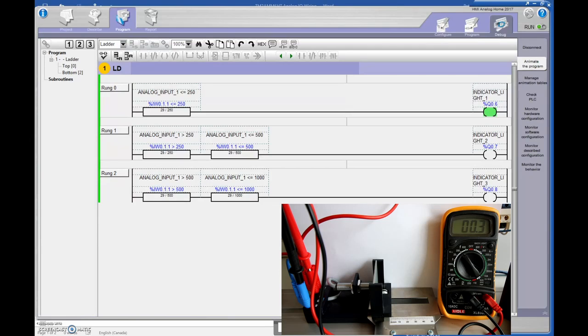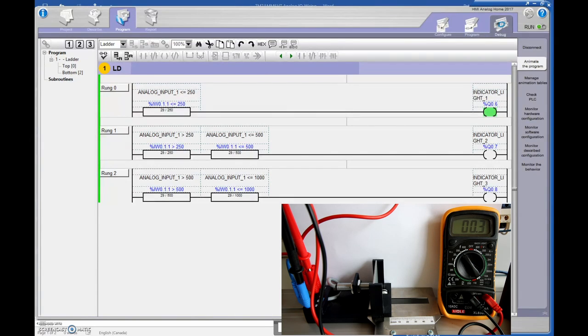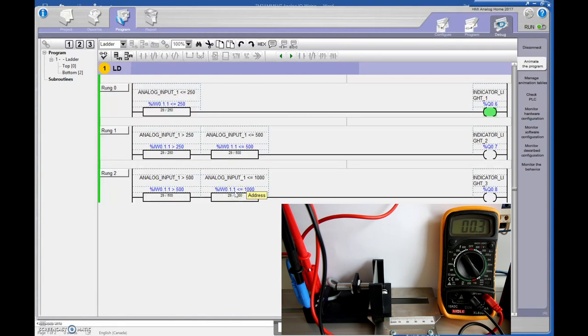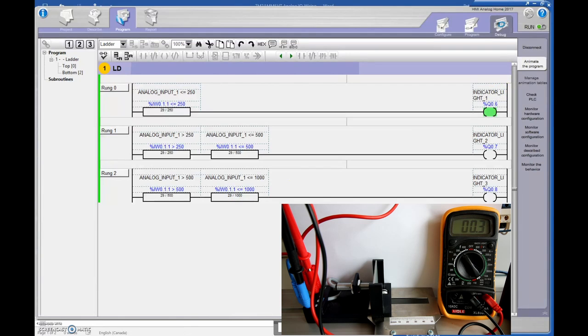And let me just move these meter leads out of the way. And right now I have the smallest distance between the sensor and the piece of steel. And so I have a basically minimal voltage there, 0.03 or 0.3 volts. So what I'm going to do is I'm going to slowly increase the distance between the plate and the actual sensor. Let me just put my PLC into run mode now. So now we're in run mode. And what I'm going to do is I'm going to slowly move the piece of steel away.